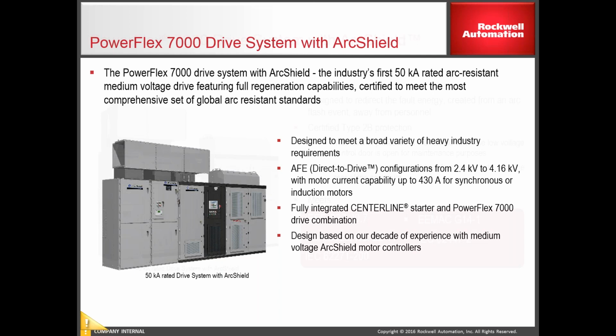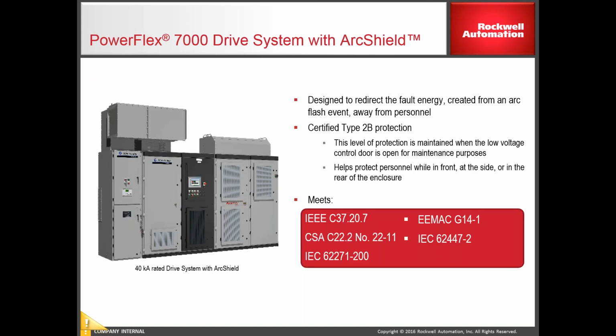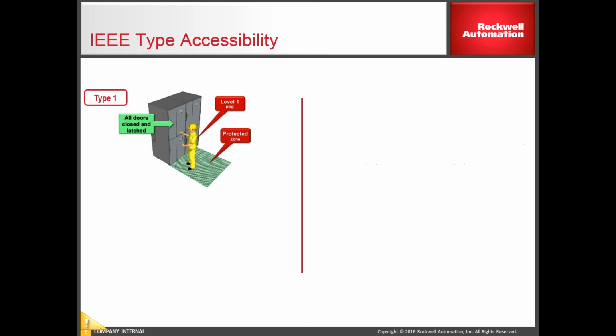It's fully integrated with the Centerline 2100 product, or the 1500 product, and it's based on decades of experience that we have with the medium voltage ArcShield motor control center. These are the standards that we build this drive to: IEEE C37, the CSA C22, there's IEC 62271. We meet all those standards with this new drive. This drive has a Type 2 accessibility. We'll talk about that in a second, and what type of protection you get with that. And really it's designed to limit the fault energy and to redirect the fault energy away from personnel.